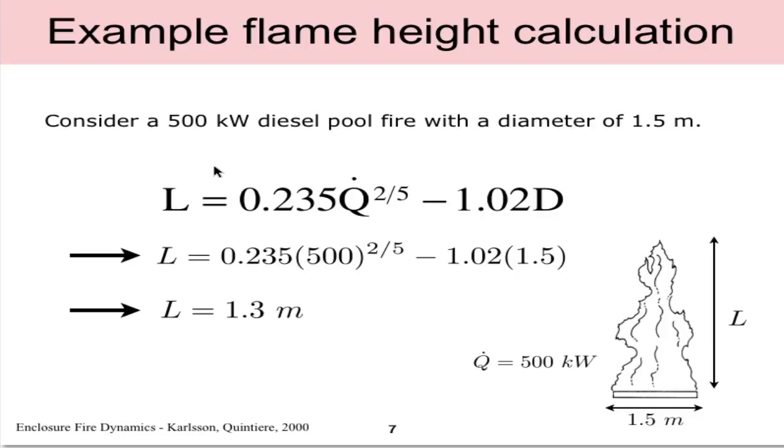Let's consider an example where we have a 500 kilowatt diesel pool fire with a diameter of 1.5 meters. If we have Q equals 500 and diameter of 1.5, if we plug those into the above equation and notice the units are consistent, 500 kilowatts, 1.5 meters, we get out a physical flame height L of 1.3 meters from this equation.